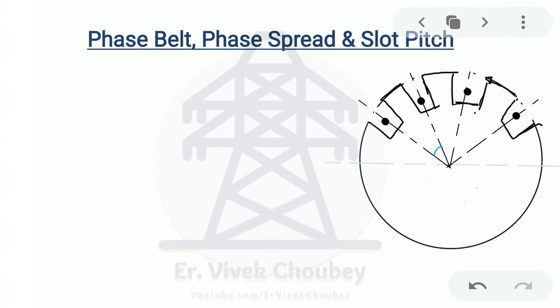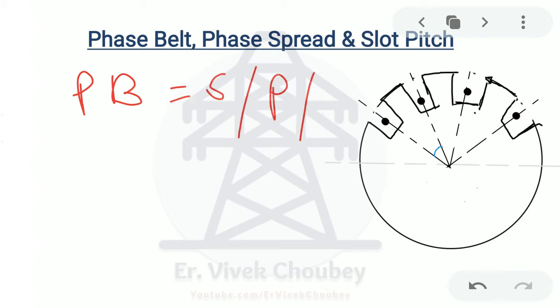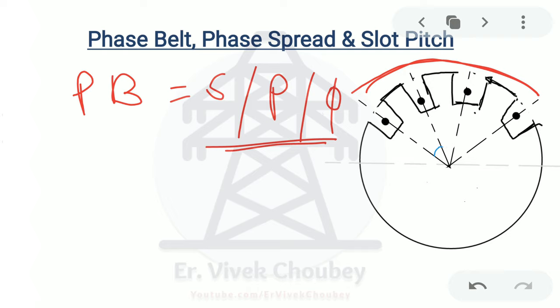Next we come to phase belt, phase spread, and slot pitch — these are allied concepts of the distributed type of winding. Phase belt may be defined as the number of slots under each pole per phase. So there is a phase winding with some slots and some poles on the machine, and each pole carries some number of slots. This number of slots per pole per phase — pertaining to one phase under each pole — is known as phase belt. In our example, the phase belt is 4.